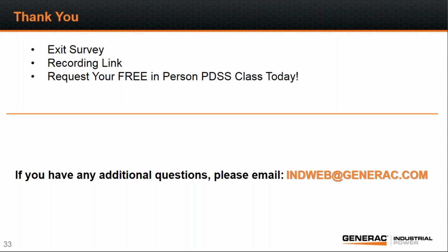Please discuss the use of active front end VFDs on generators. What is the max % of total load that can be AFE VFDs? Yeah, an active front end implies regenerative power capabilities, similar to the elevator discussions we were having. Usually a generator can only brake about 10% of its rating. So a 100 kW generator is usually about 10 kilowatts of reverse power. Anytime you have active power factor front ends that you're going to regenerate with, you're limited on that. We would normally recommend other connected loads.